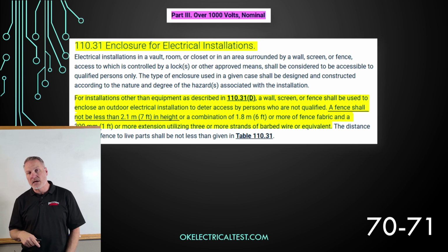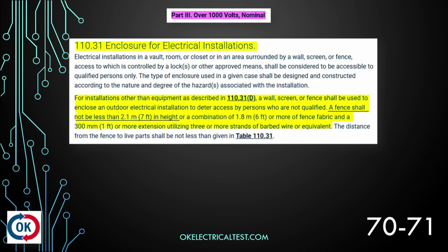We're going to skip down to the second paragraph, and it says, for installations other than equipment described in 110.31(D), a wall, screen, or fence shall be used to enclose an outdoor electrical installation to deter access by persons who are not qualified. A fence shall not be less than 7 feet in height, or a combination of 6 feet or more of fence fabric and a foot or more of extension utilizing 3 or more strands of barbed wire or the equivalent. So it's saying in this installation that's enclosing electrical apparatus that's operating at over 1,000 volts, that fence needs to be 7 foot high. Or you can make it 7 foot high, right? 6 feet plus 1 foot is still 7 feet.